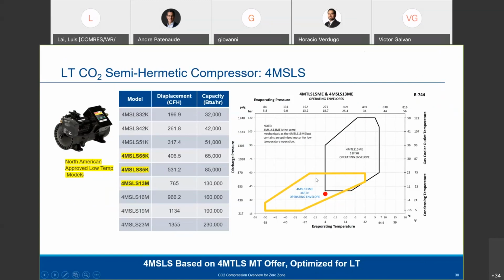But when you look at the operating envelope here, you can go down to -58 Fahrenheit. Like the ZO scroll, it can go as high as about 32, but your envelope gets narrowed here when you do that because you don't have a lot of head pressure left. So you're good for up to 870 pounds or 60 bar on the head pressure. This is a typical operating point, -20 and about 35. That's 35 bar, which is almost 35 degrees with CO2.